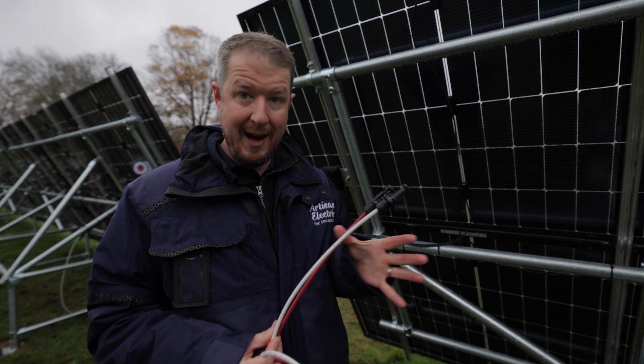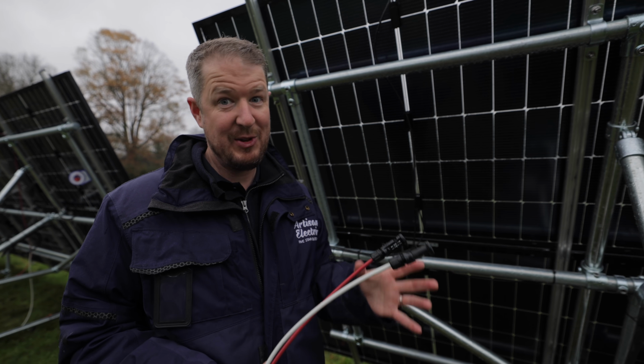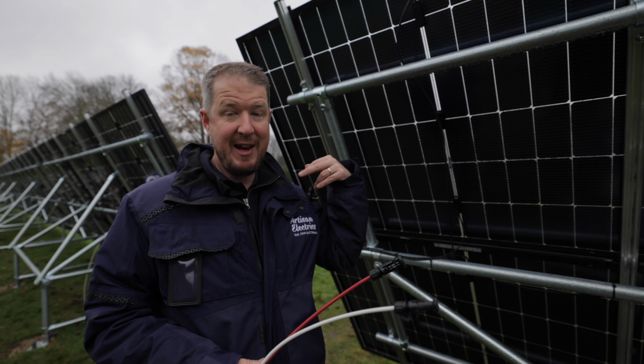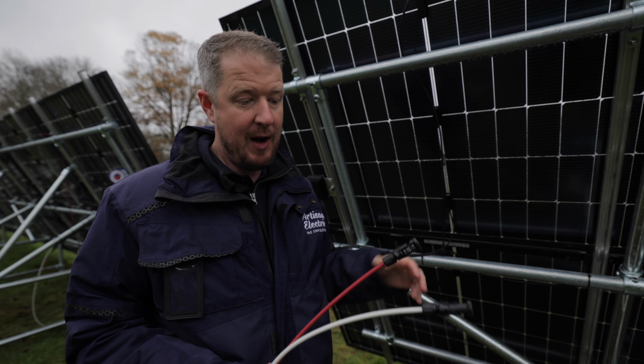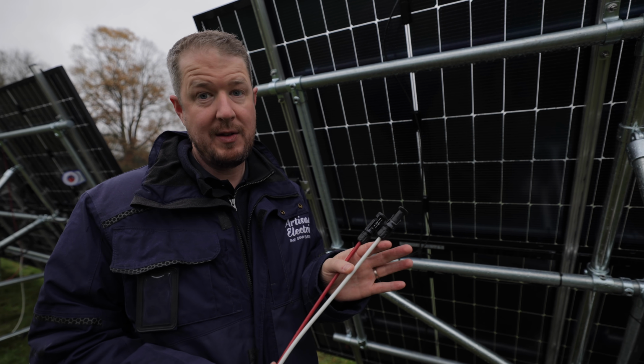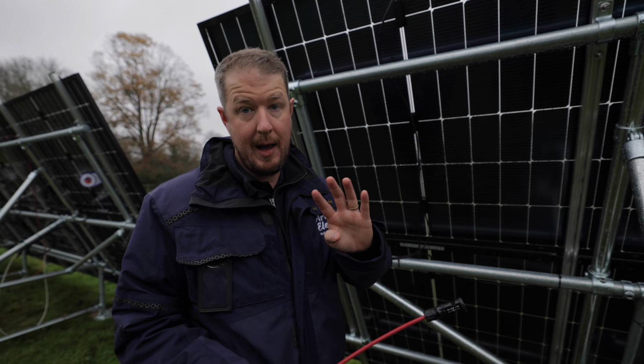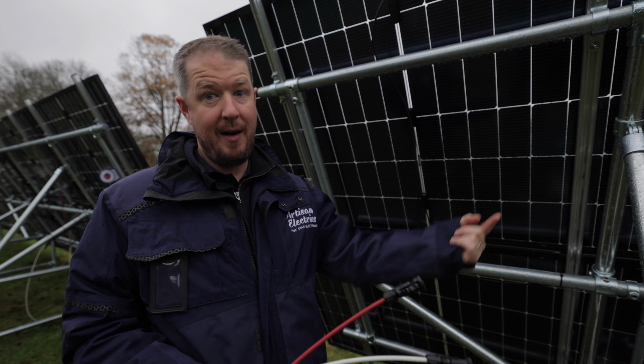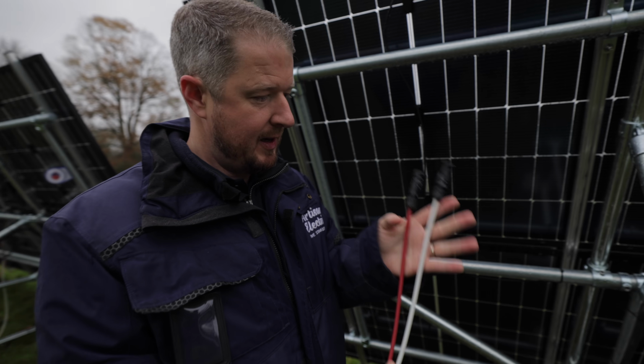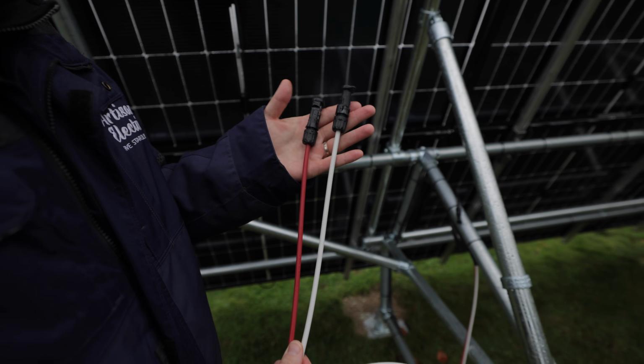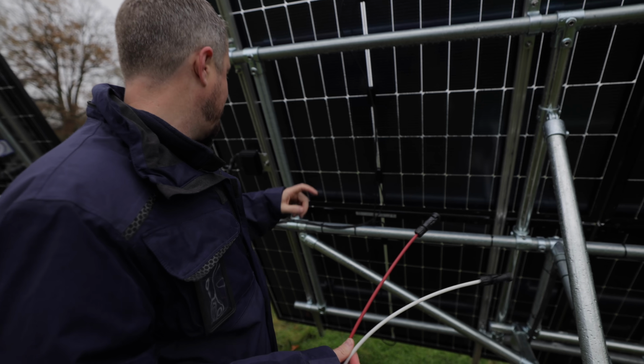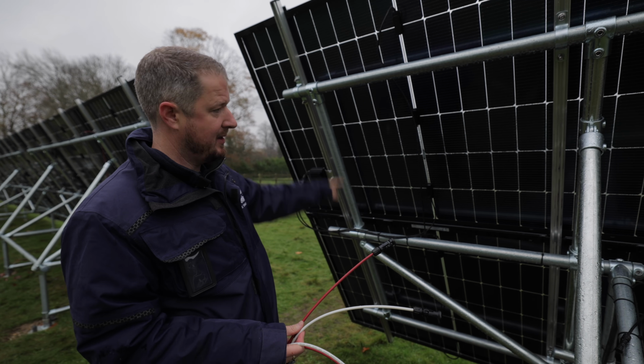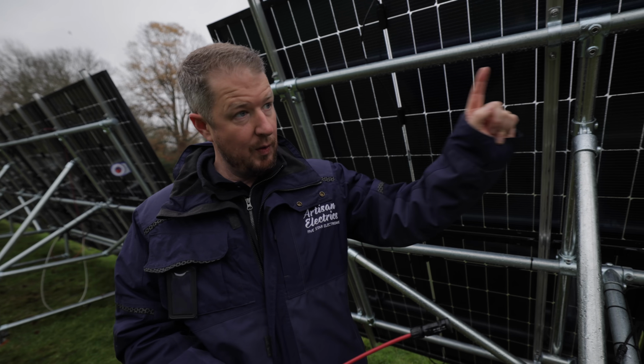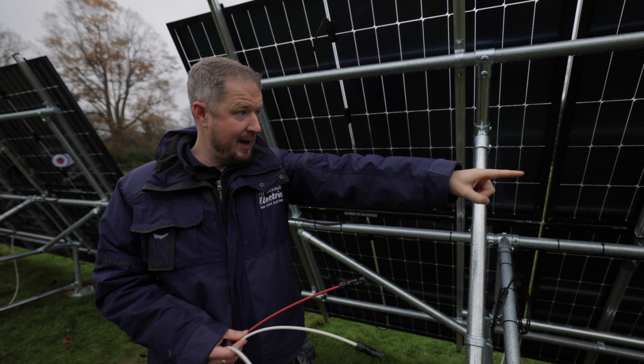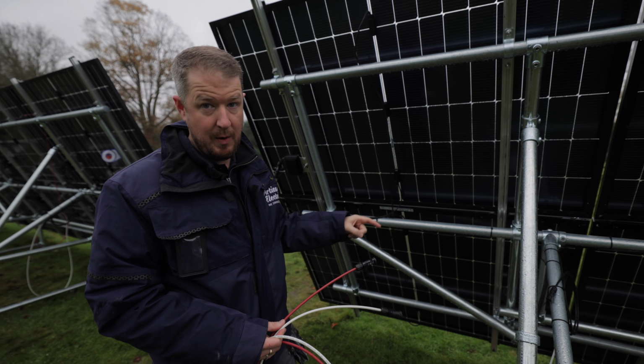How we've arranged the wiring of these panels is also interesting, and tricky to get right. We've designed each bank of 30 panels so it can be one string on the SolarEdge inverter, which has 4 MPPTs - 4 strings that can input into it. This 2-core PV Ultra cable is one string, connecting this optimizer which serves 2 panels, then continuing along the top, 2 panels per optimizer, dropping down at the end, and then back along the bottom, again 2 panels per optimizer.